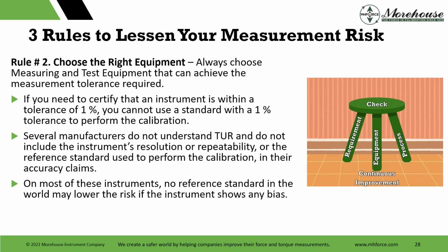Several manufacturers just don't get this. They don't understand TUR, the test uncertainty ratio, or if we go to JCGM 106, we call it measurement capability index. They don't include the really important pieces of measurement uncertainty, like the resolution of the unit under test or repeatability, or they don't even include the reference standard used to perform the calibration in their accuracy claims.